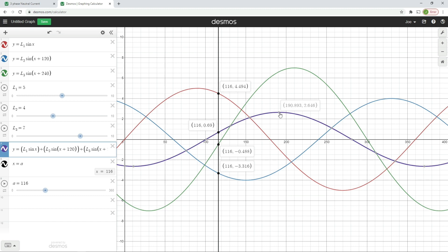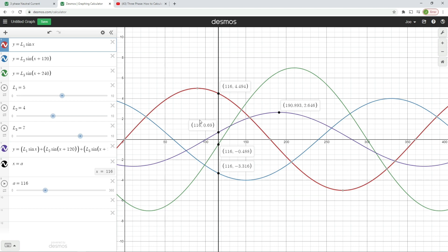The handy thing is that where the purple waveform peaks at 2.646, that value is actually what we would calculate as the neutral current. So if you go back over my previous videos on calculating neutral current, put those L1, L2 and L3 values in, and you'll find where the waveform peaks — that is the calculated neutral current. This has value in two ways: it helps you see what's happening when we add waveforms together, and you can use it to check your answers when doing self-directed study and exam practice. I'll put a link in the description.